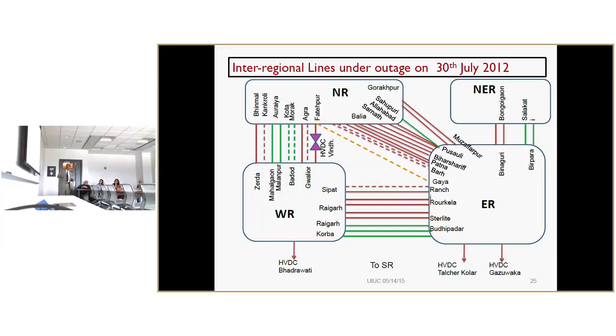So when this line was carrying a large amount of power, finally at early morning 2:33, one of the distance relay protections operated because of load encroachment. So it came into the zone 3 protection, and that operated and tripped that line. When that line also tripped, there were a few weak lines, because of oscillations between this region and the western region, they tripped one by one.